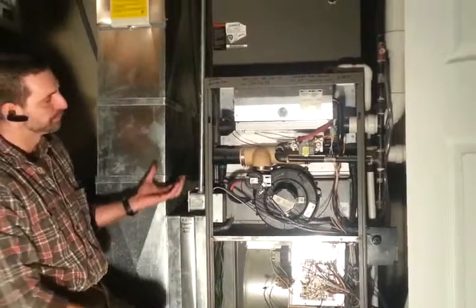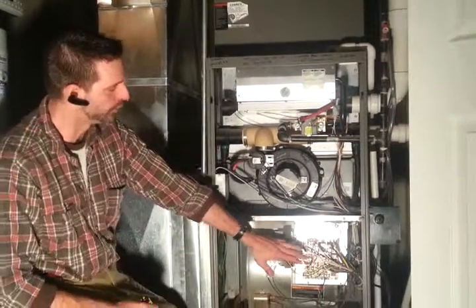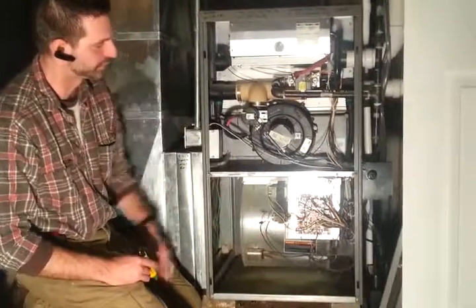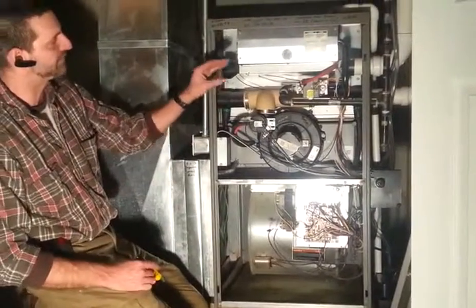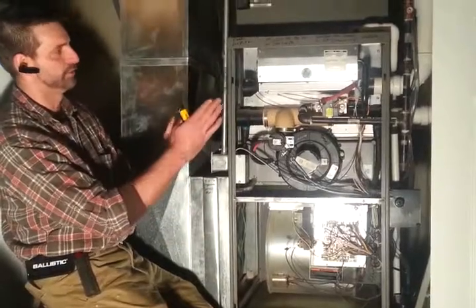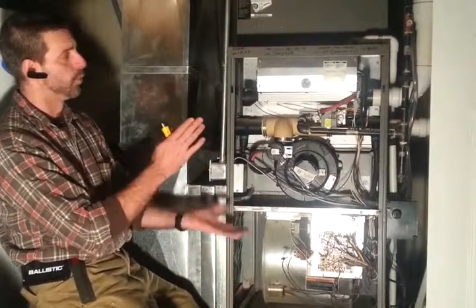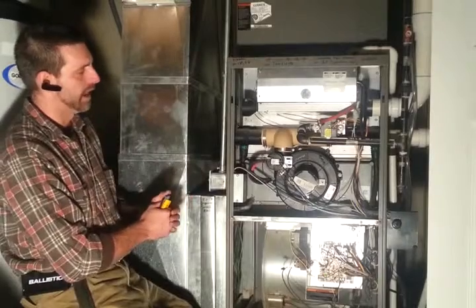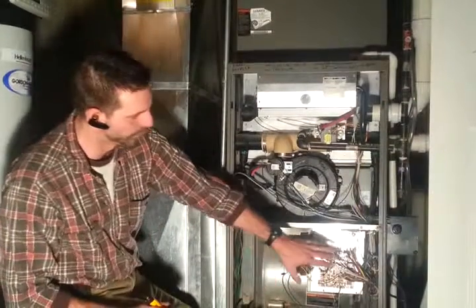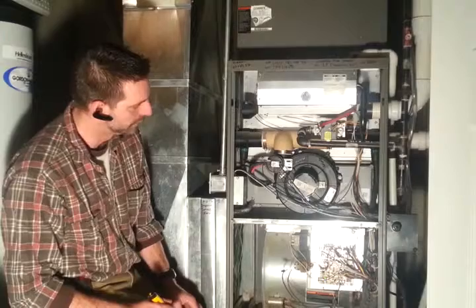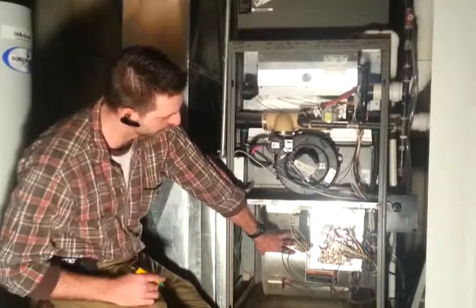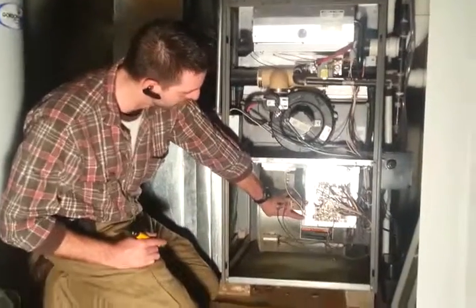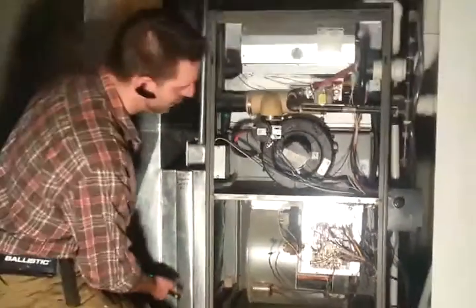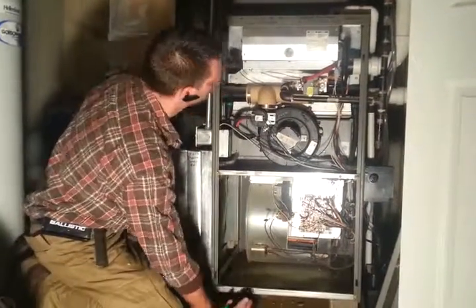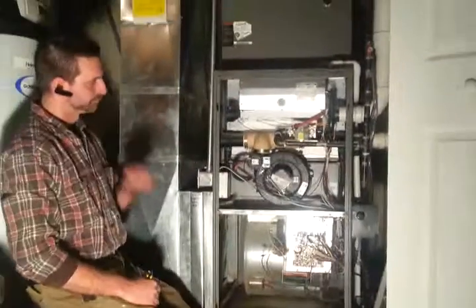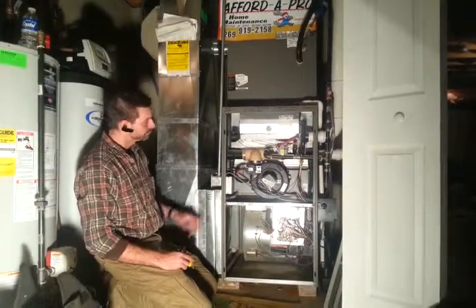Once they heat up, mine is actually controlled via a timer built into the control board. Some of the older furnaces had fan switches. So they would actually monitor the temperature of the heat exchanger. Once it reached a certain temp, then it would turn our blower on. The newer ones are all done by time. So once that time expires, which it just did, you can hear this blower kicked on. Now that my heat exchanger is nice and hot, I'm pulling air in across, taking it up across my heat exchanger, up and out. So that's the basic operation.